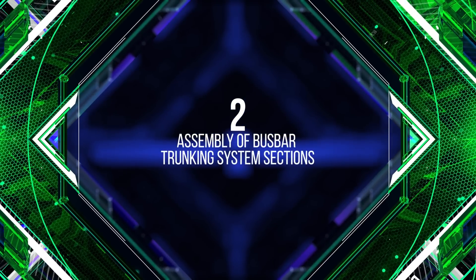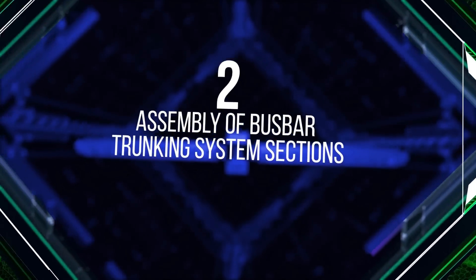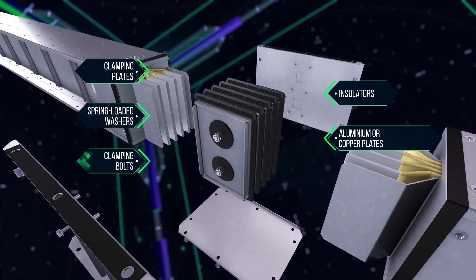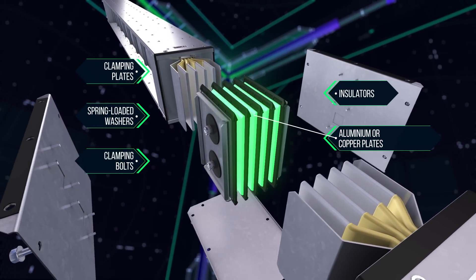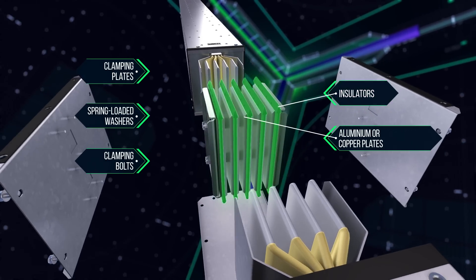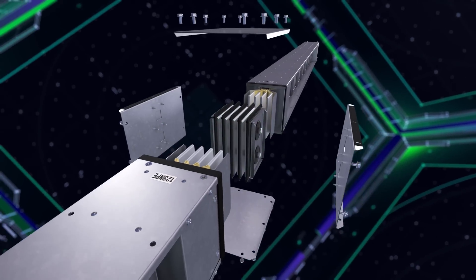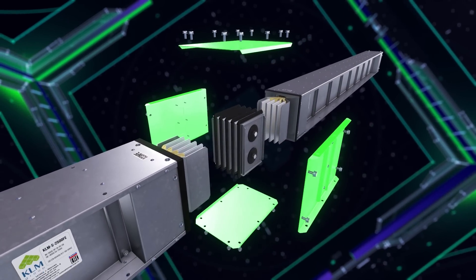Assembly of bus bar trunking system sections. Connect the sections using a junction unit consisting of aluminum or copper plates insulated from each other, insulators, clamping plates, bolts with spring-loaded washers, and top, bottom, and two side covers with plugs.